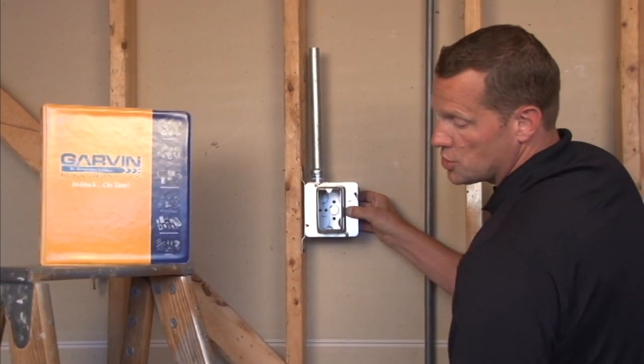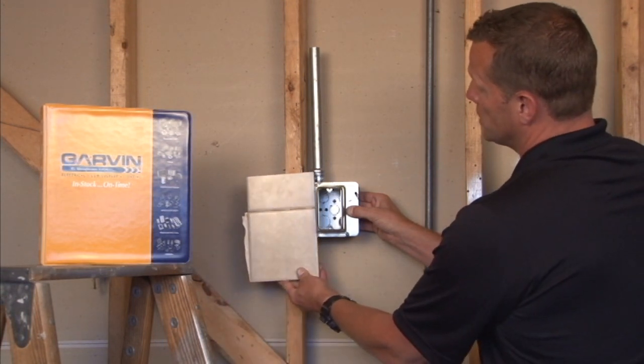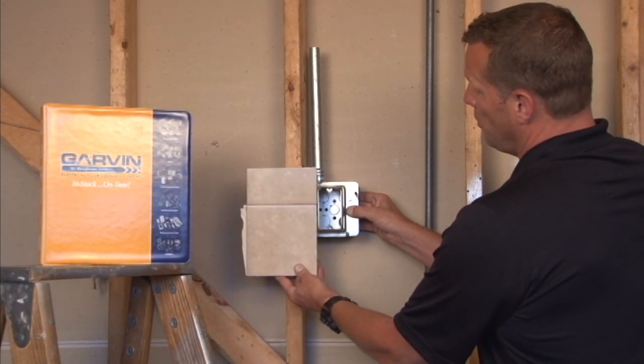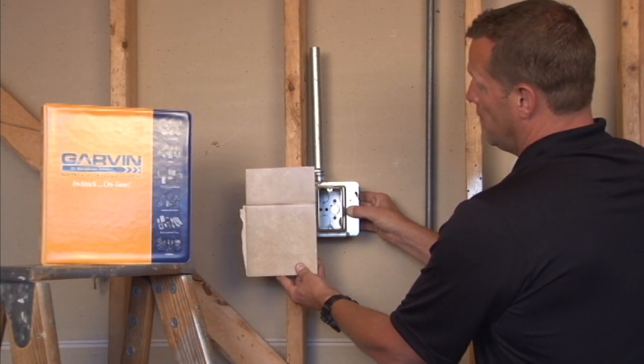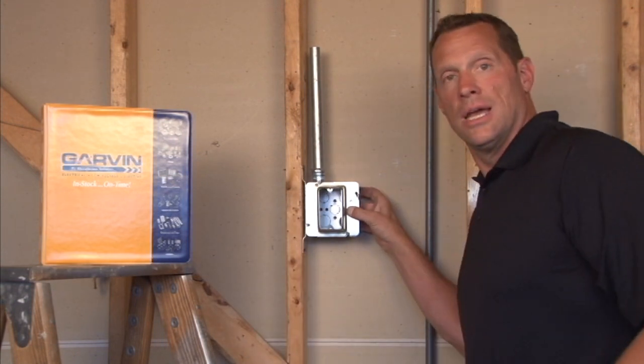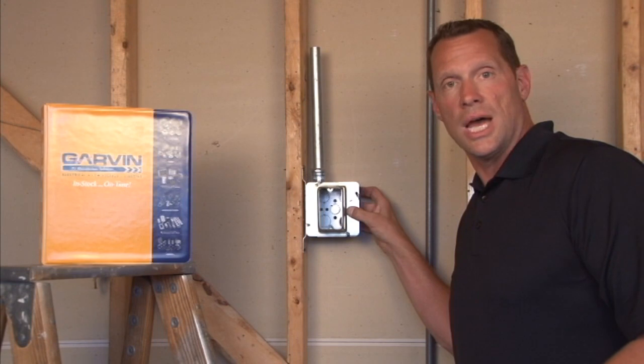Very important to remember when choosing a two inch raised ring: your finished wall surface must come all the way up to the edge of the ring, or your devices may not install properly. For these and other great products and a full line of device rings, visit us online at GarvinIndustries.com.